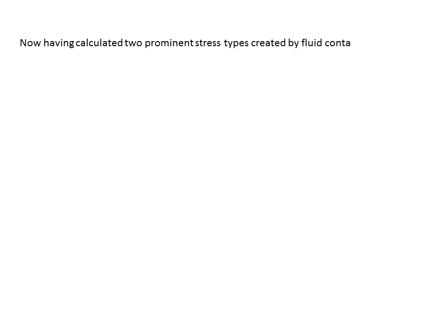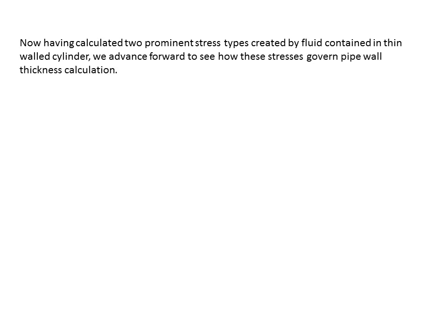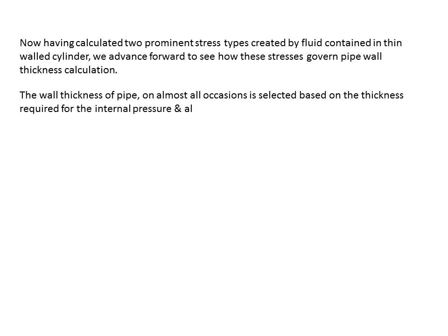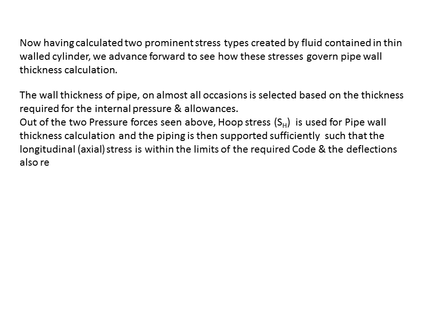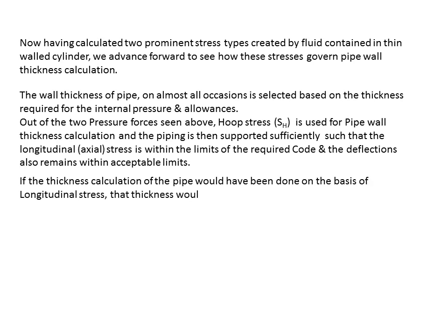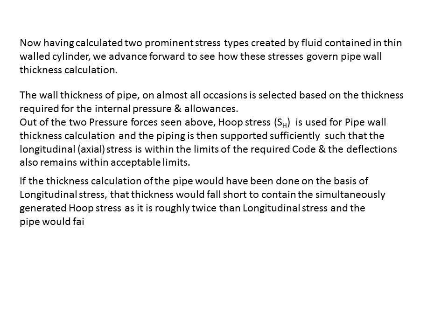Having calculated the two prominent stress types created by fluid in a thin-walled cylinder, we now see how these stresses govern pipe wall thickness calculation. The wall thickness is almost always selected based on the thickness required for internal pressure plus allowances. Hoop stress is used for pipe wall thickness calculation. The piping is then supported so that axial stress remains within code limits and deflections remain acceptable. If thickness were based on longitudinal stress alone, it would be insufficient to contain the simultaneously generated hoop stress — roughly twice as large — and the pipe would fail circumferentially.